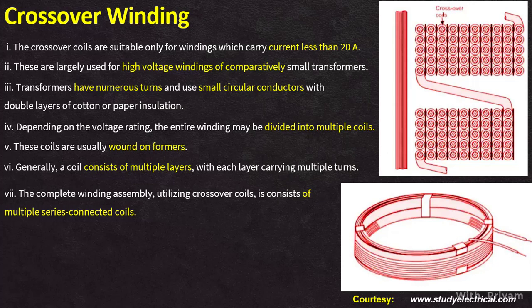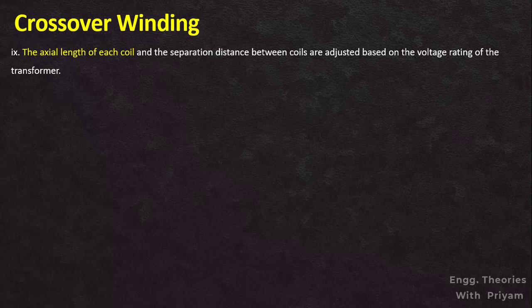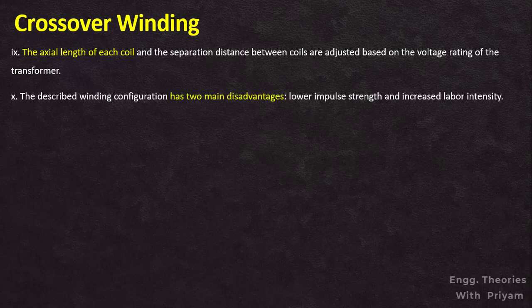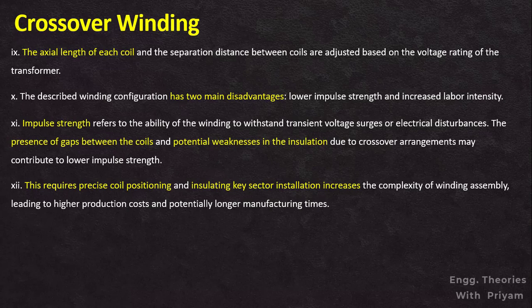The assembly is positioned over the limb of the core. Insulating key sectors are used to separate the coils and create gaps between them, allowing free oil circulation for efficient cooling. The axial length of each coil and the separation distance between coils are adjusted based on the voltage rating of the transformer to optimize performance and electrical characteristics. The crossover winding configuration has two main disadvantages: lower impulse strength and increased labor intensity. Lower impulse strength means reduced ability to withstand transient voltage surges, while the need for precise coil positioning and insulating key sector installation increases manufacturing complexity, production cost, and potentially longer manufacturing times.